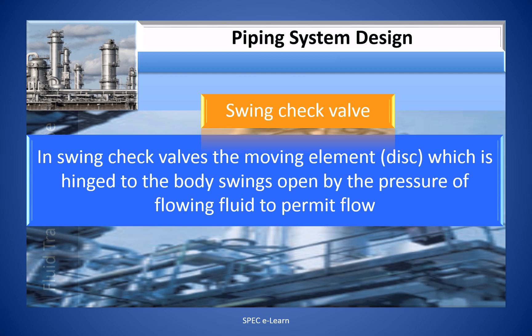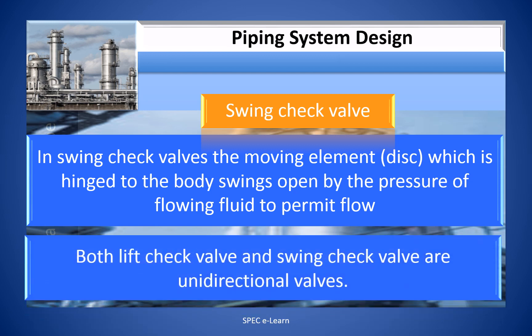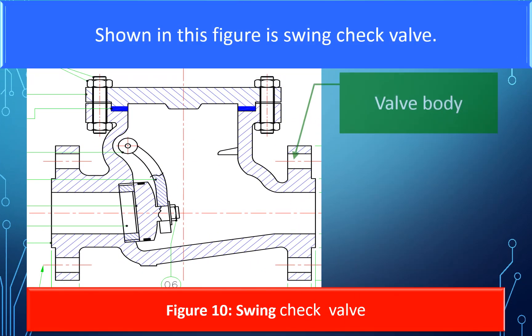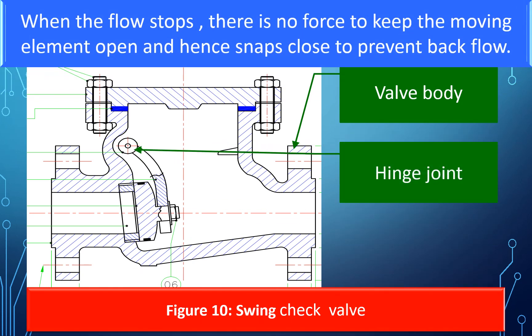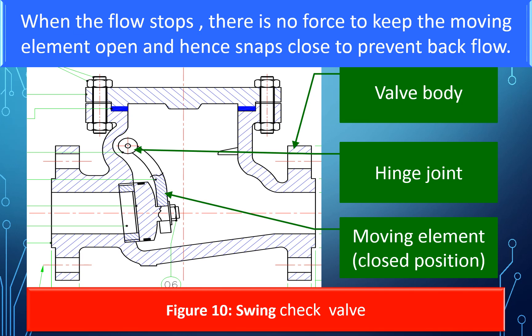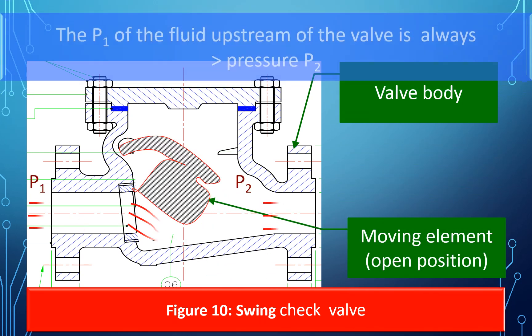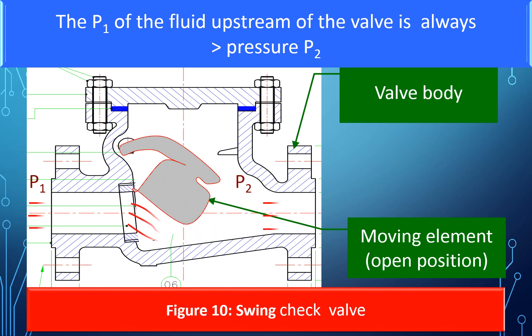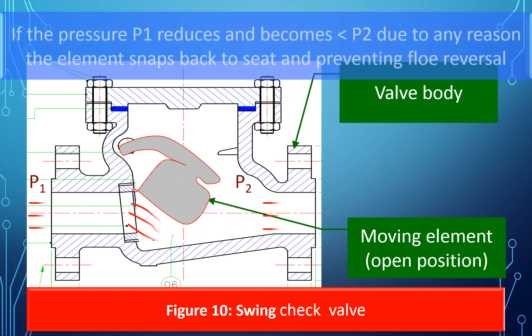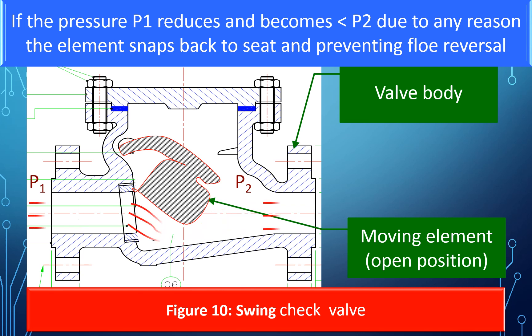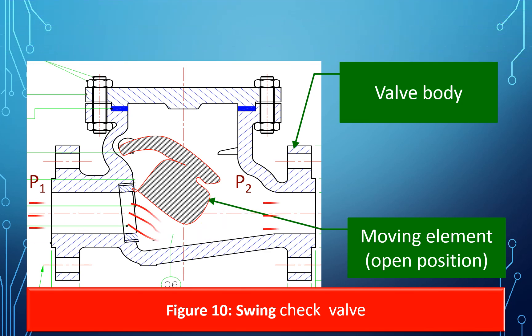In swing check valves, the moving element or disc is hinged to the body and swings open by the pressure of the flowing fluid to permit flow. Both lift check and swing check valves are unidirectional valves. When the flow stops, there is no force to keep the moving element open. The pressure P1 of the fluid upstream is greater than pressure P2. If P1 reduces and becomes less than P2 for any reason, the element snaps back to the seat, preventing flow reversal.